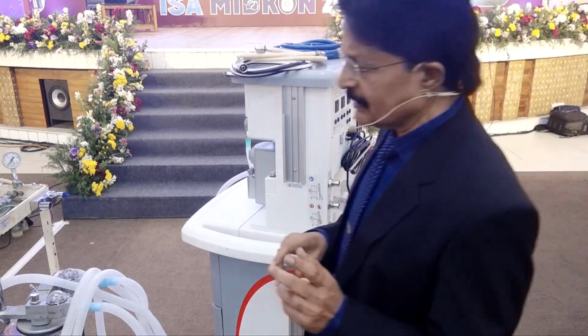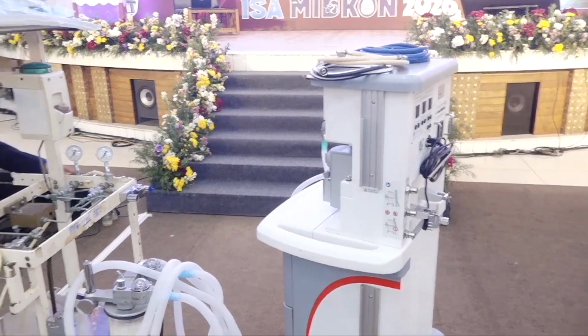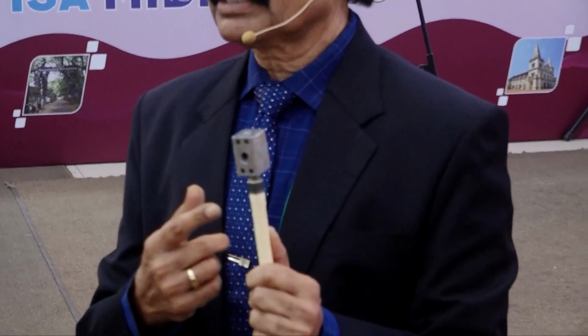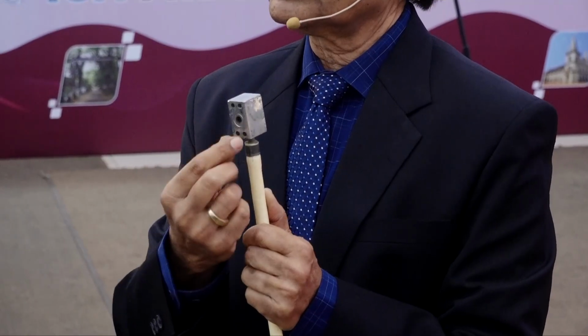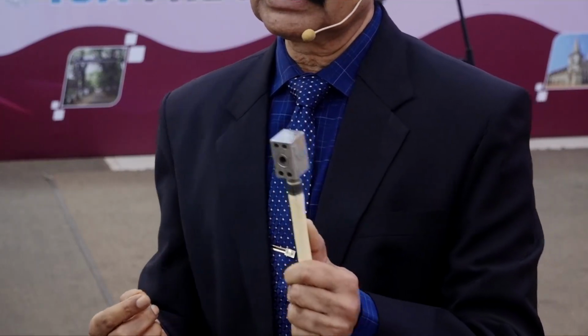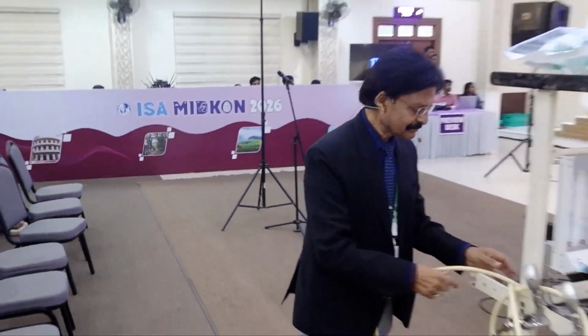That is one thing. The second thing is they'll also ask you about what is called a yoke block. It's good that they have one here. This is called a yoke block. You would not have seen it, because you can see the pin index holes are there. In the older machines, the pipelines were connected to the same yoke where you connect the cylinder, because to connect the pipeline you require the pin index holes. For oxygen, it is the second position and the fifth position. This is called a yoke block, and that is a yoke plug. So just remember that.